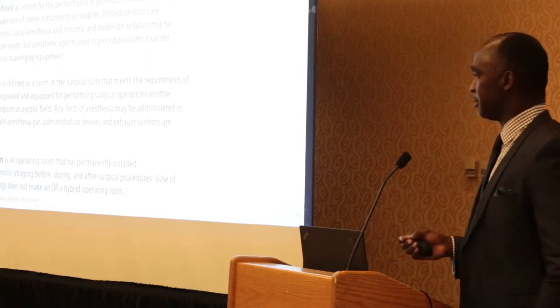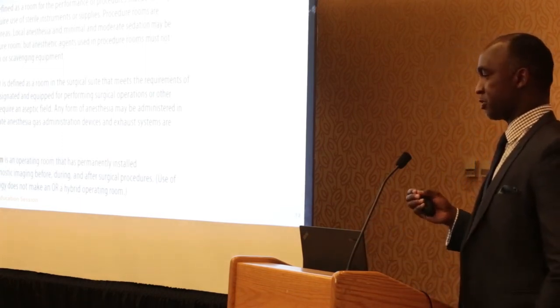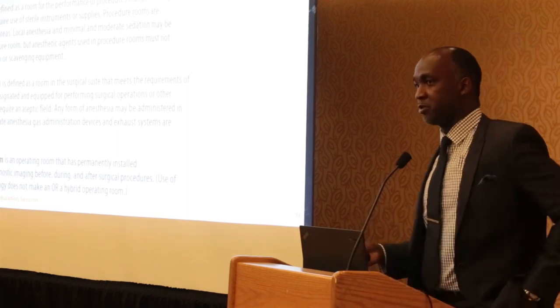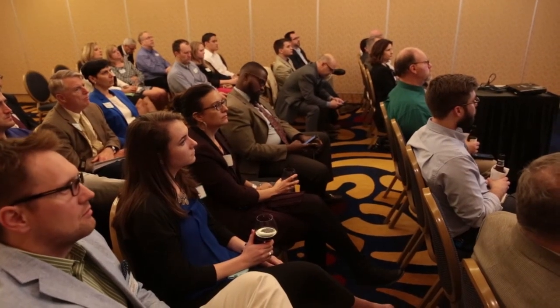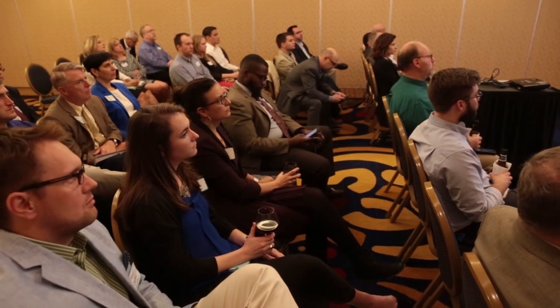The operating room now talks about restricted areas, and that's extremely important—a restricted area means you have to be gowned down before you actually enter that room. That's the biggest change in the code.